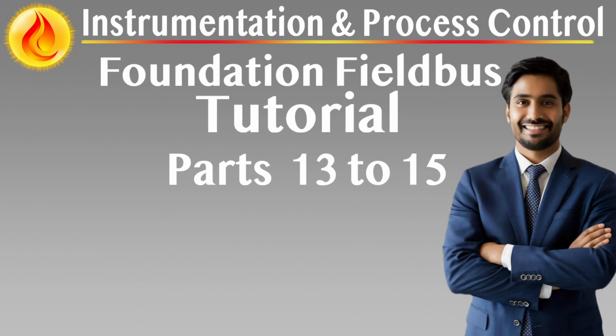commissioning and maintenance. Capability files, CFF, complement the DD by defining the device's communication behavior, specifically how many function blocks it supports, the block types, their execution timing, and the scheduling model. The CFF provides the host with static configuration data needed for offline engineering, including VCR requirements, resource capacities, memory allocation, and macrocycle compatibility. It is particularly important for automated segment configuration and resource planning during project design.